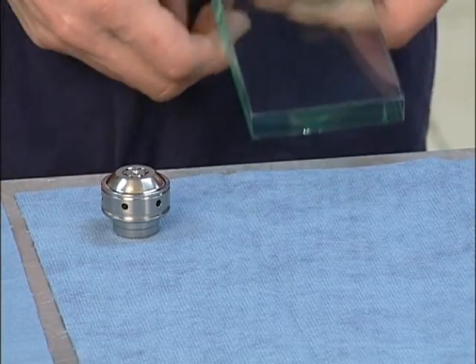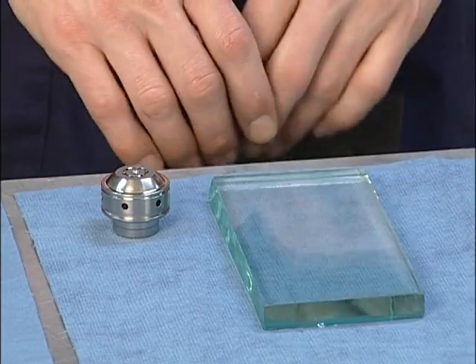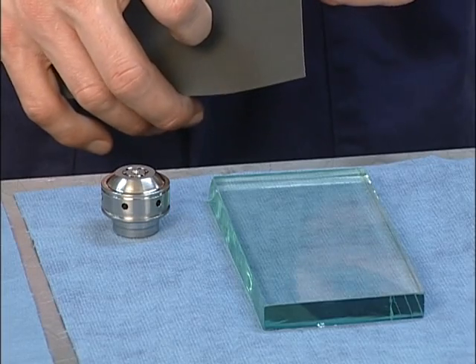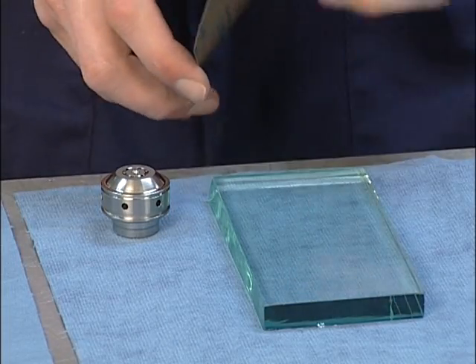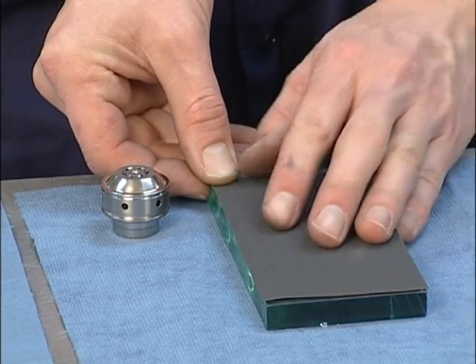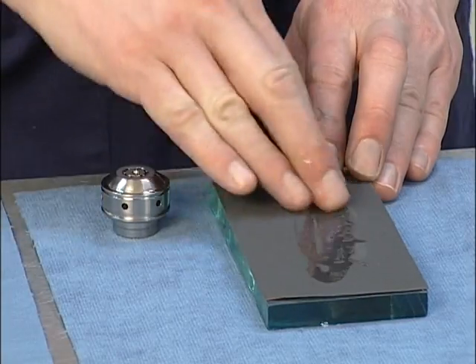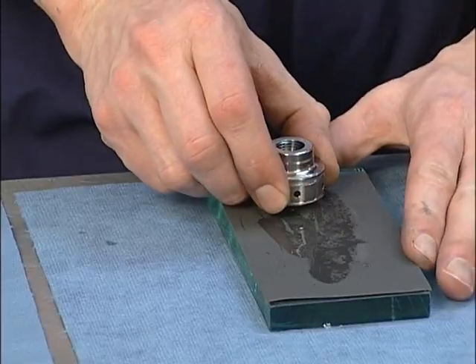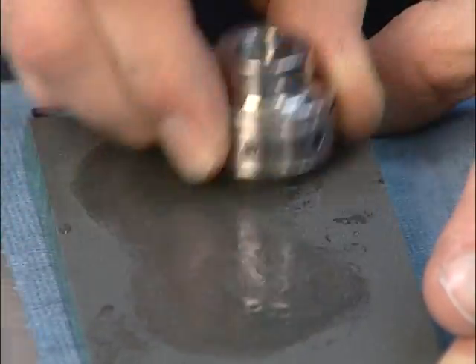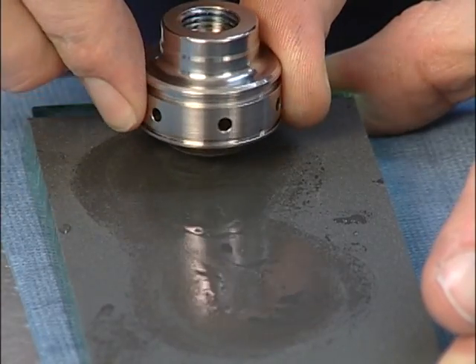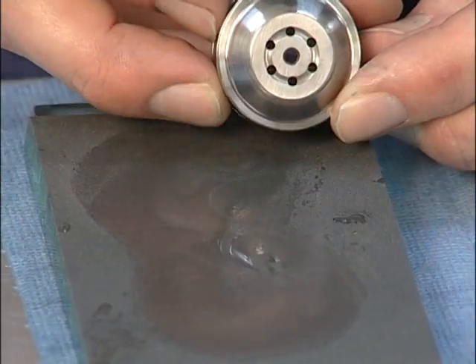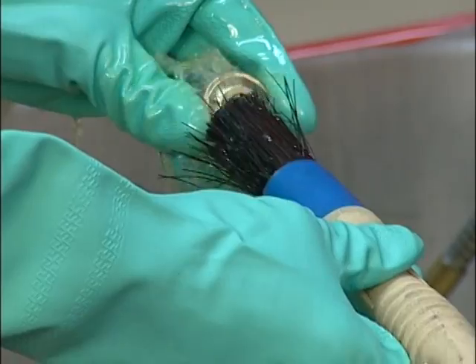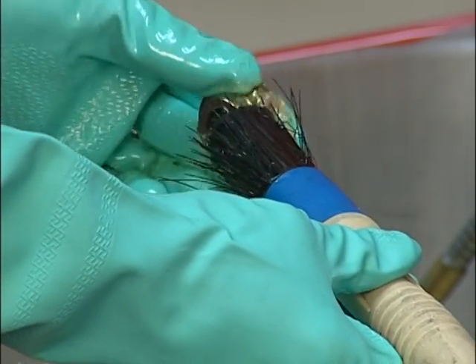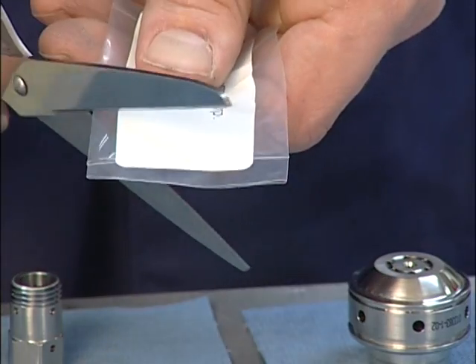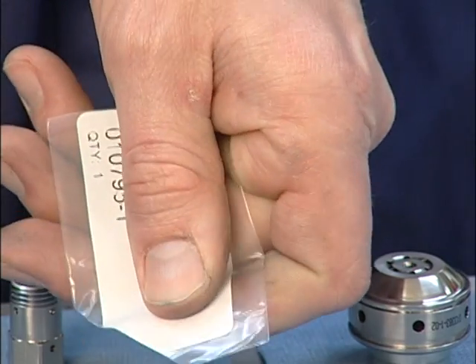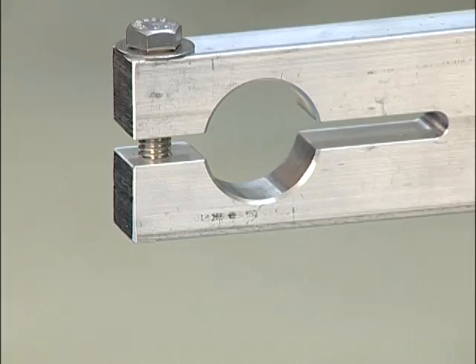To lap the inlet face of the check valve body, attach a piece of 320 grit adhesive-backed abrasive paper to the glass lapping plate and place a few drops of water onto the paper. Using a figure-8 pattern, lap the check valve face until all wear or damage is removed and the entire check valve surface has been lapped. After 10 to 12 lapping motions, rotate the valve body 45 degrees. Remember, flatness is critical. If the face is not flat, the inlet poppet will leak. Clean the part thoroughly to remove any abrasive particles from the face and bores. Reassemble the check valve.